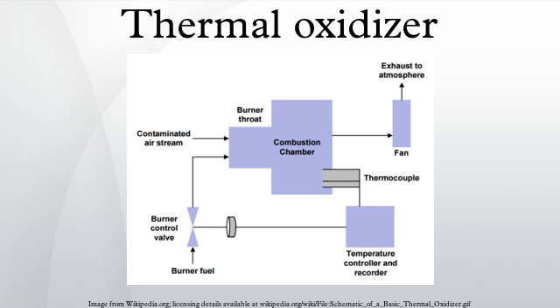Such biomass fired thermal oxidizer has been installed at Warwick Mills, New Hampshire. The inlet concentrations are between 3000-10,000 PPM VOC. The outlet concentration of VOC are below 3 PPM, thus having a VOC destruction efficiency of 99.8%-99.9%.